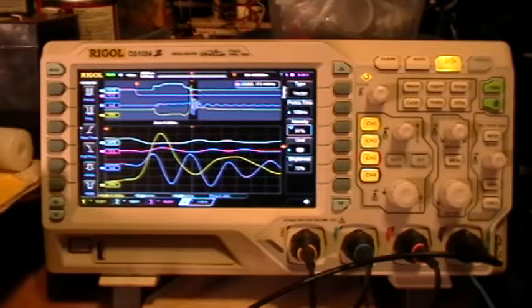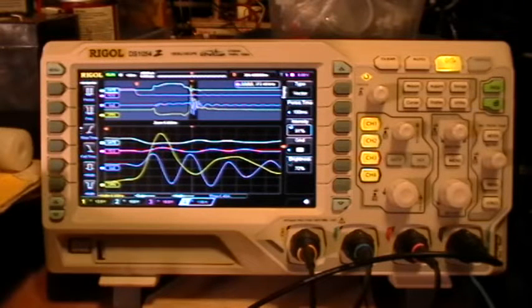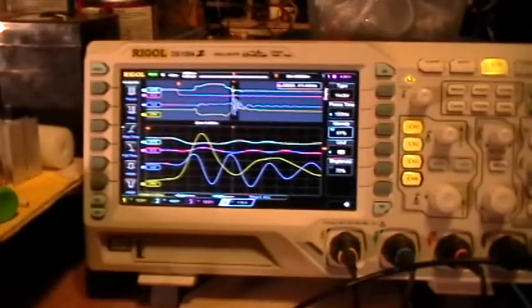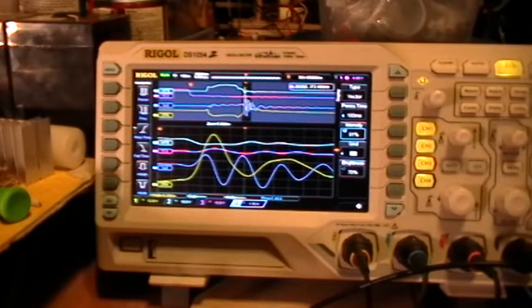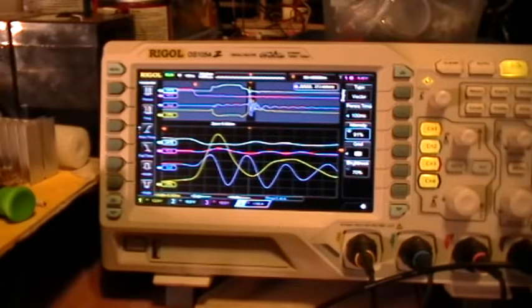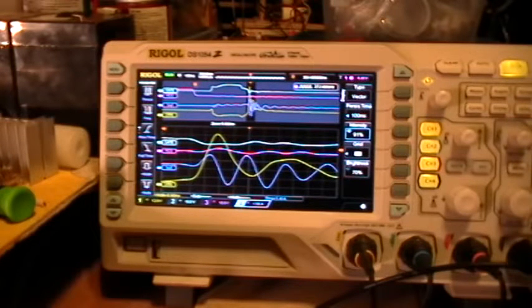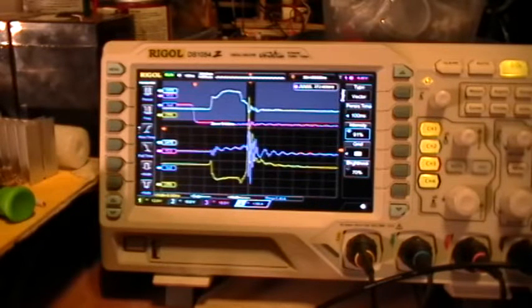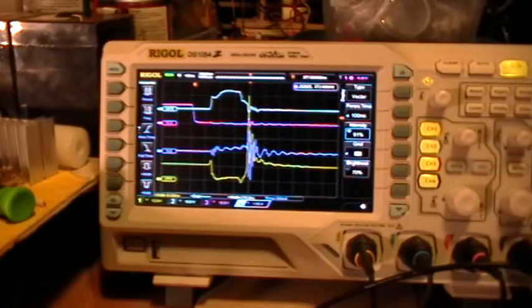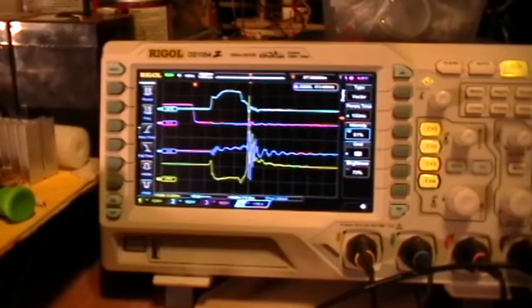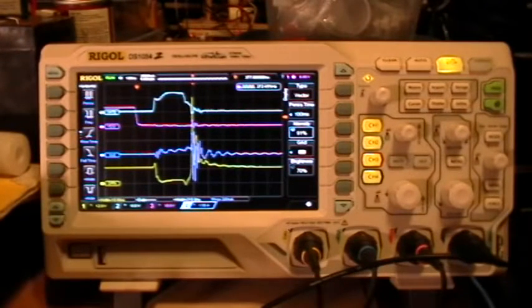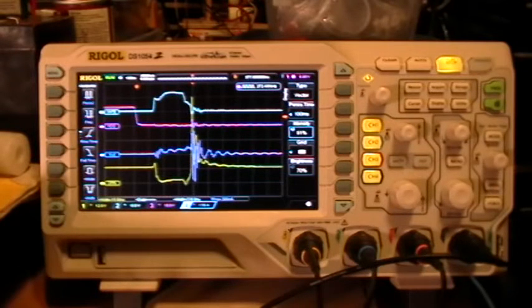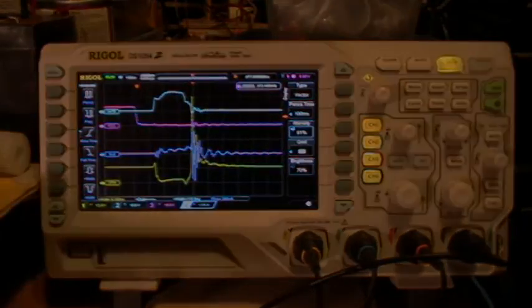Now let's go back to Time Base Main Scale 100 nanoseconds, and then we'll go back to Time Base Delay Scale off. And there we have it. Remote Control and use of Averaging and persistence time to get a nice clean signal from a jittery one. Thanks for watching.